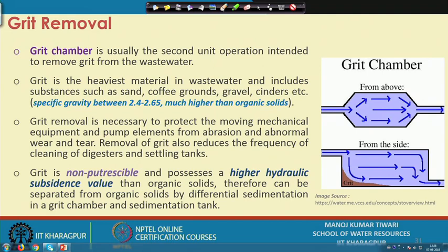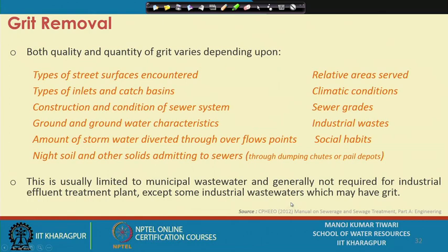In primary sedimentation, the target is to settle finer settleable solids. Grit can be easily settled due to its very high specific gravity. If allowed through, a significant mass of the sludge will consist of grit only, requiring frequent cleaning of the sludge zone. Since grit possesses a higher hydraulic subsidence value than typical organic solids, it can be easily separated from organic solids by differential sedimentation in the grit chamber, while subsequent sedimentation takes place in the sedimentation chamber.